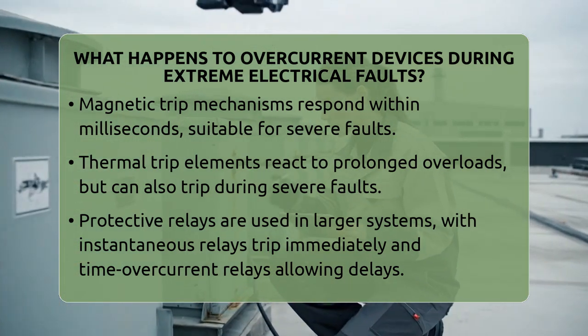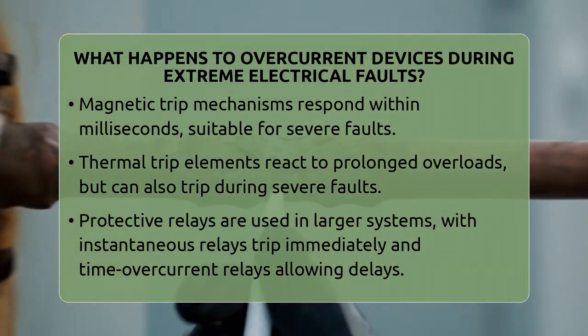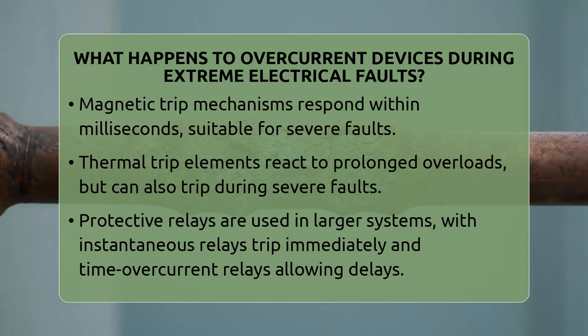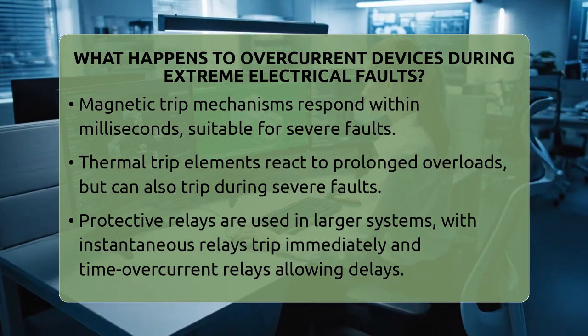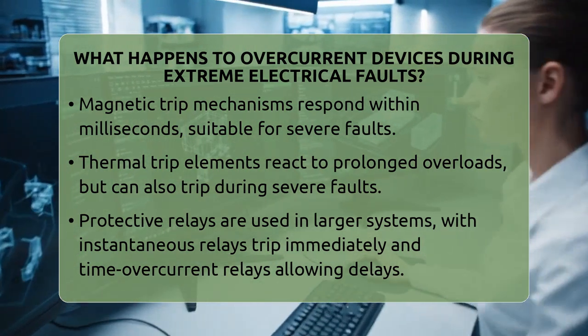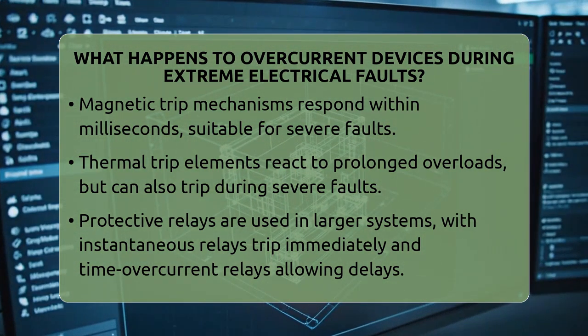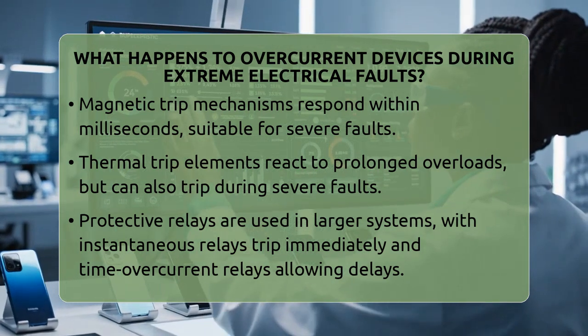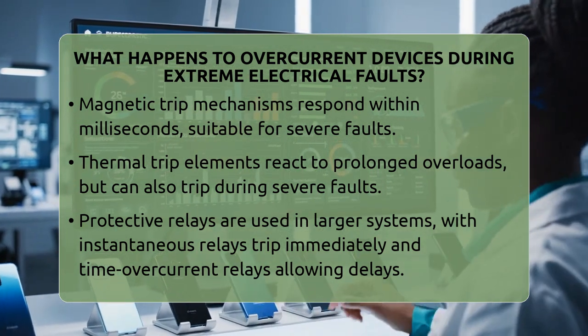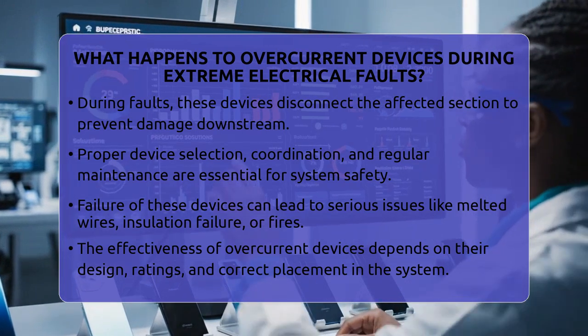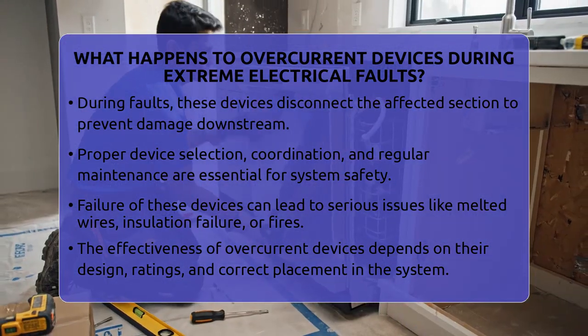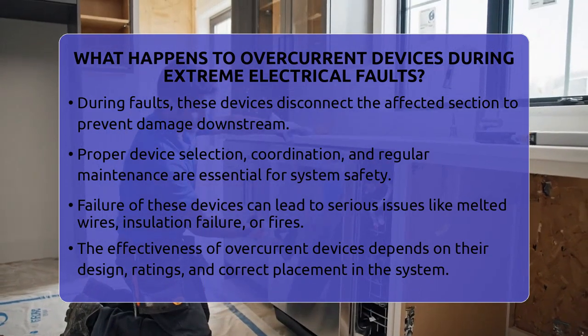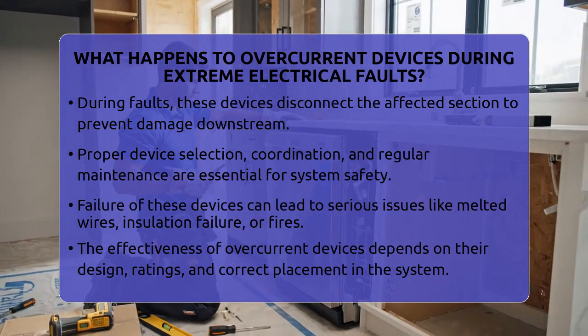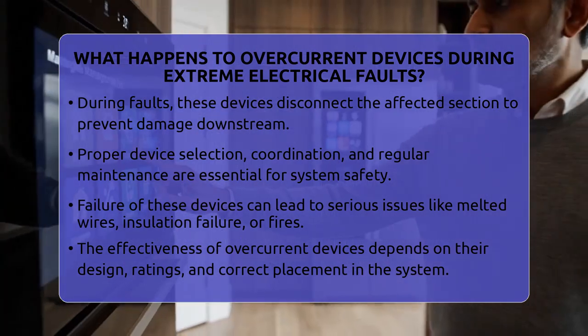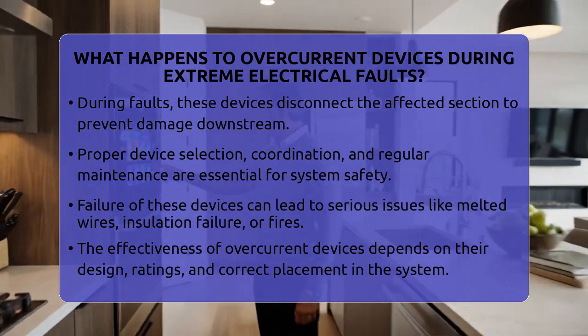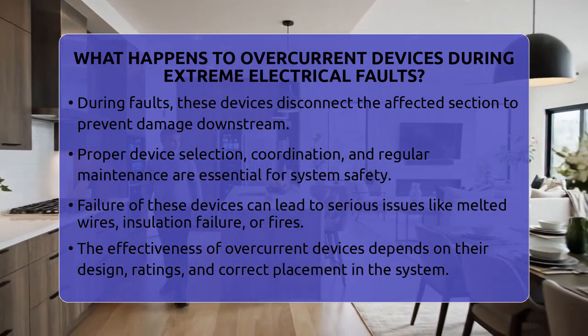When the device trips, it isolates the faulted section, stopping the flow of electricity and protecting the rest of the system. If the device fails to operate properly, the fault can cause serious damage like melted wires, insulation breakdown, or even fires. The key to effective protection is choosing devices with enough interrupting capacity to handle the maximum possible fault current. Proper coordination between devices ensures that only the faulty section is disconnected, keeping the rest of the system running smoothly. Regular inspections and maintenance are essential to make sure these devices work when needed.